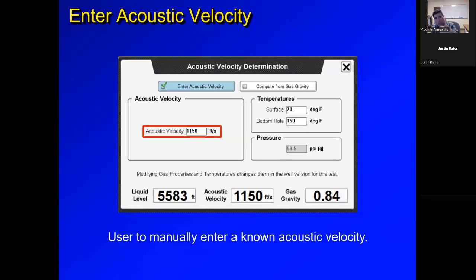Last option: let's say you don't have collars to count. This is the worst case scenario. You don't have collars to count, you don't have any marker, and you don't even know the gas composition, you have no idea about the gas. So the software still needs an acoustic velocity. What we do then is tell the software, I want to input the acoustic velocity, because I don't have any means to calculate it. If you click there, the software by default will show 1150, but that 1150 is just a software default. It doesn't represent your average in your area.